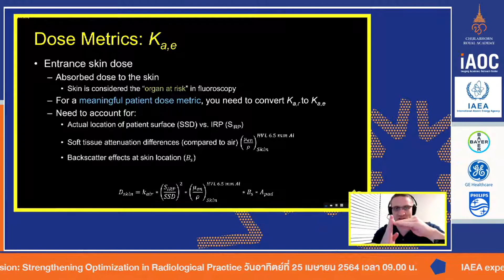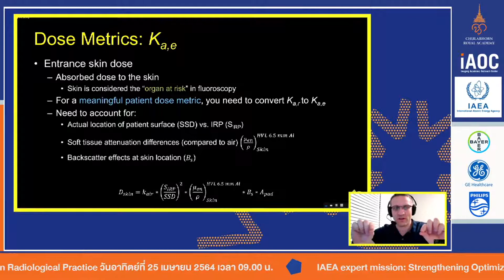We need to know how much the radiation attenuation will change as it goes from air exposure, as it enters the body and goes into the skin. So there is a ratio of how much attenuation will change as it goes from air to skin. And we need to account for the fact that there's a lot of backscatter. In other words, when that radiation hits the skin, some of it is going to penetrate in a little bit and scatter back out. Once it goes into the body, it has the potential to come out and dose the dermis layer. So there is a backscatter component.